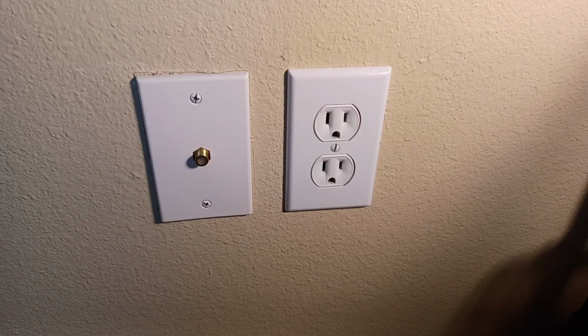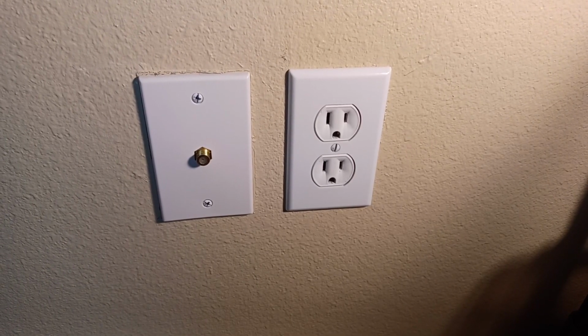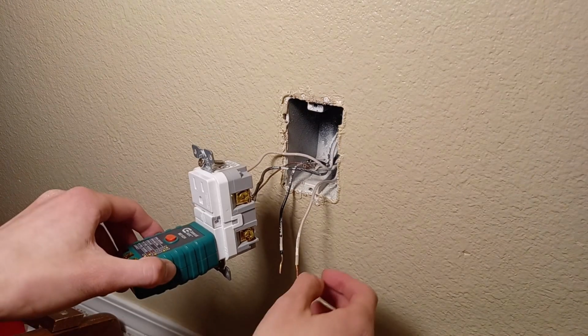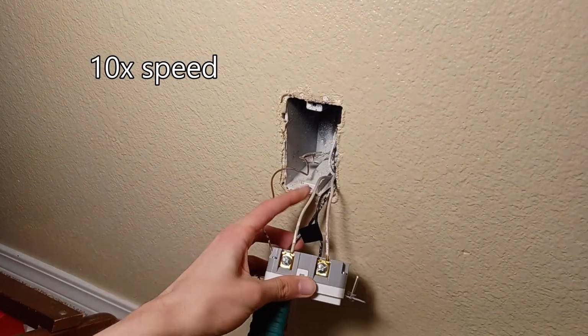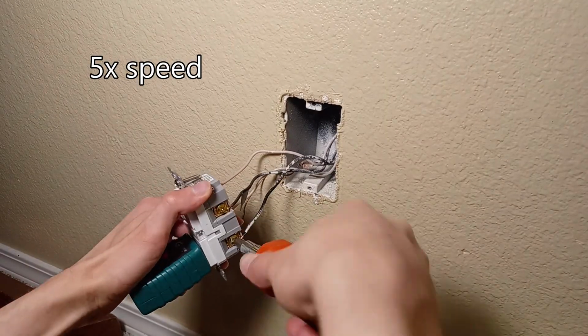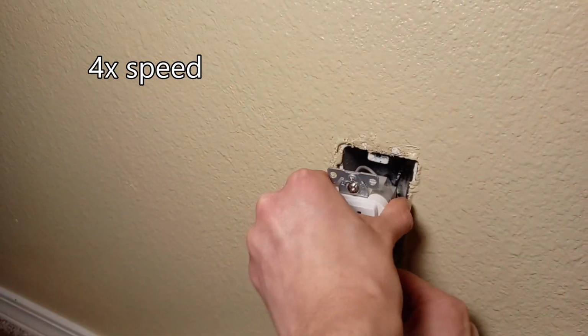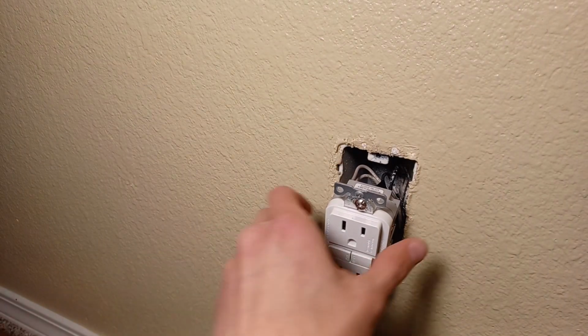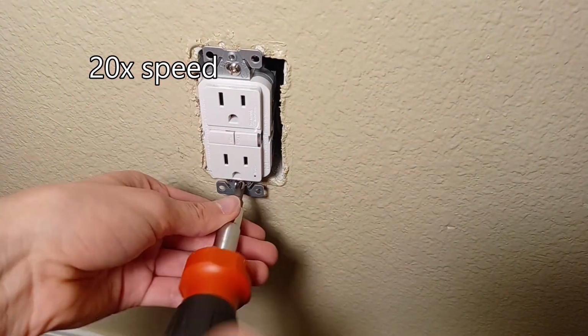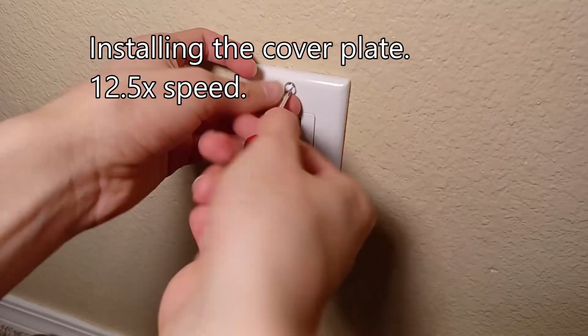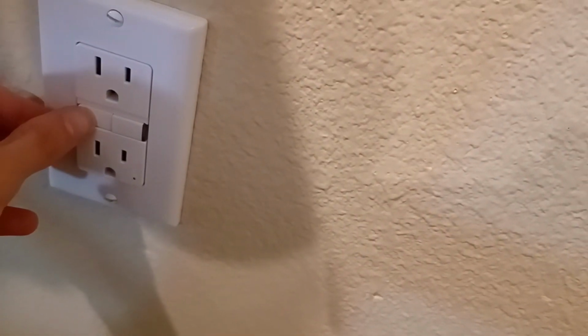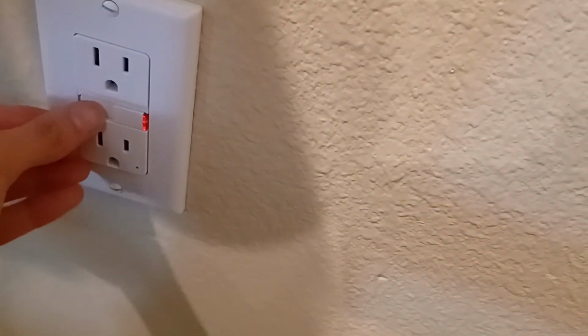Now, it shouldn't be shorting ground to neutral, so I hope that makes it not trip. Let's try. Well, now that I fixed that, let's put this back together. Let's make sure the neutral does not touch ground on this one. There we go. Looks good. How about this? Now, will it insta-trip? No. It's holding. The test works, but does get stuck. That holds, so I think it's good. Let's try here. We're good.